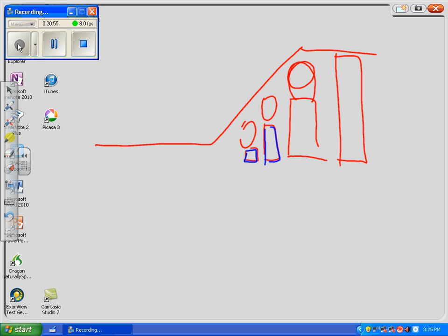And then, worse yet, there's another piece of pipe up here running across your path above where you have to go. So what I'm saying is you have a small window of opportunity to get through. Sometimes this happens, where you can only get through at that one point right there. What you do is take a test piece of conduit, the size you need to get through there, and slide it in. Then you take a level on it and level it up, and you get a measurement down to the ground, the level that you're going to be running the other conduit on.